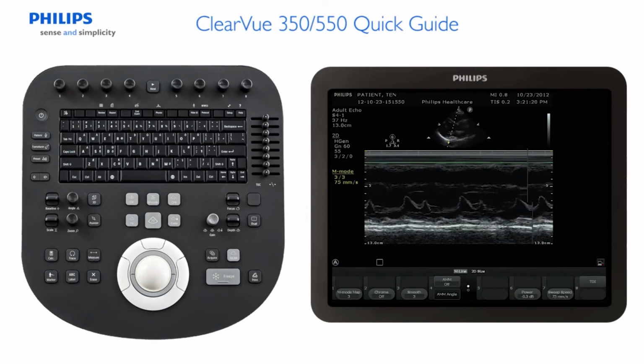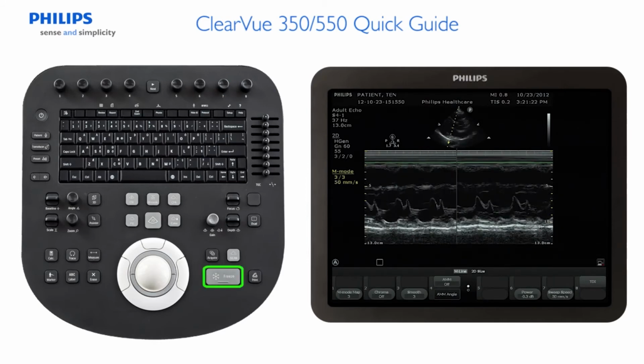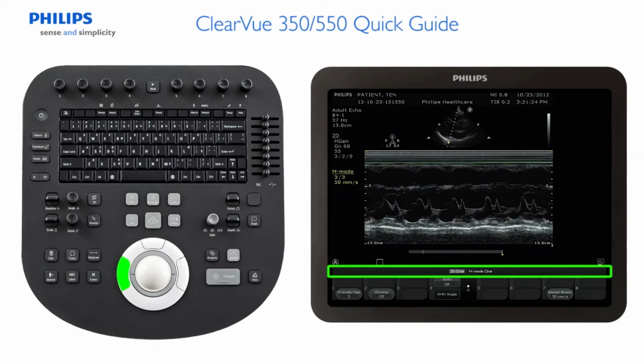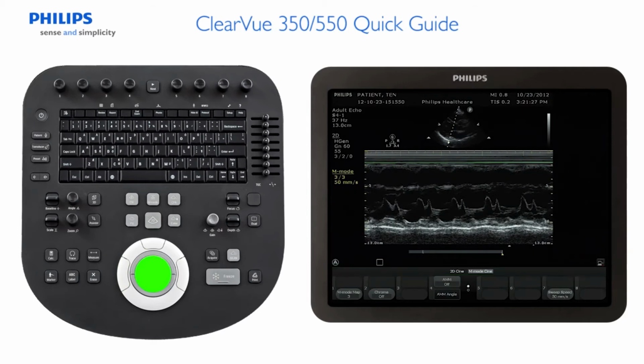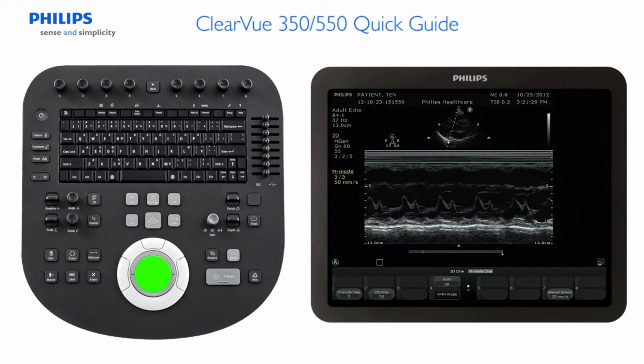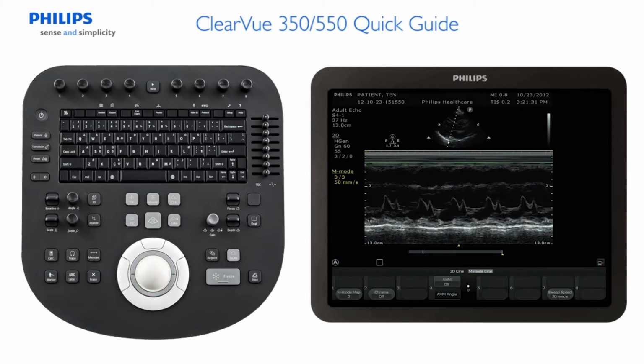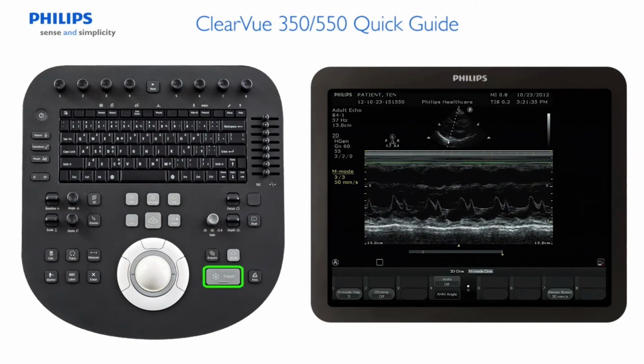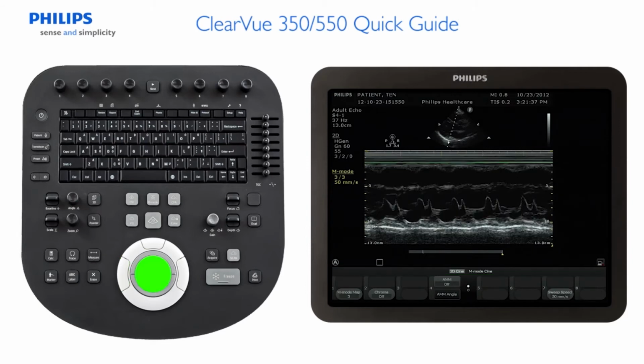To review the M-Mode trace, press Freeze, select M-Mode Cine, and use the trackball to scroll forward or backward. To review both the M-Mode trace and the 2D data, press Freeze, select 2D Cine, and use the trackball to scroll forward or backward. To exit M-Mode, press 2D.